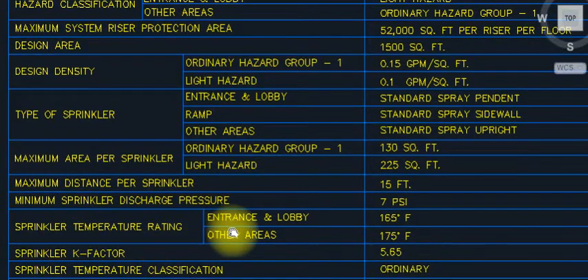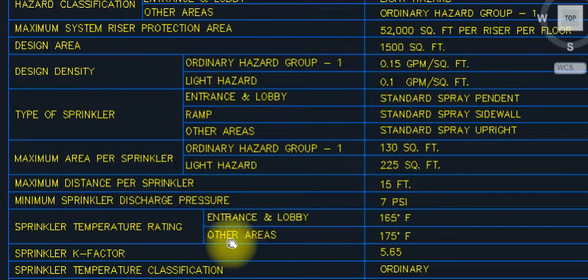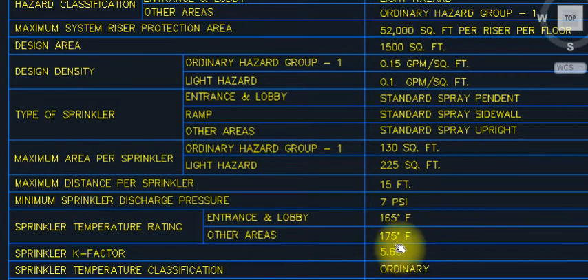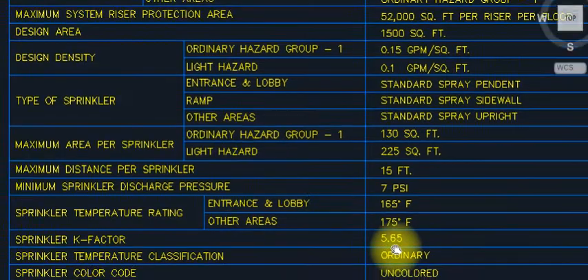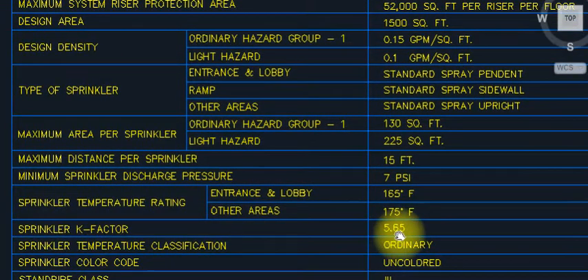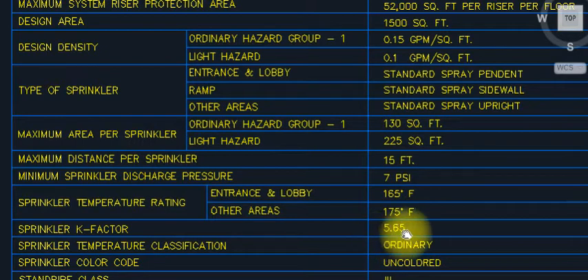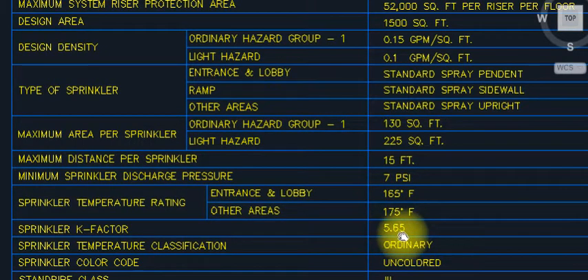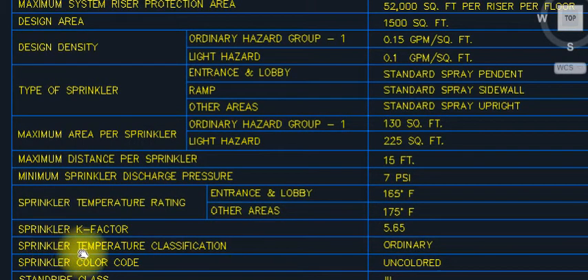Sprinkler temperature rating: entrance and lobby — 165°F; other areas — 175°F. Sprinkler K-factor: 5.65. Keep this in mind — this is the K-factor for sprinklers.